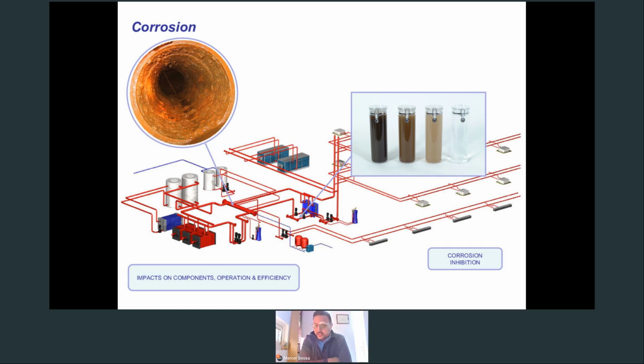Research suggests that just a 2 millimeter layer of corrosion actually reduces the heat transfer efficiency by as much as 5%. And the indirect impact of corrosion is particle generation, and these particles begin to clog up heat transfer surfaces and components. So passivation is key, and the conventional way of passivating surfaces is to use corrosion inhibitor chemicals during the startup of a system, the filling stage, and then to dose as required throughout the operational life of those systems. So corrosion inhibition is done in reference to BSRIA guidelines.